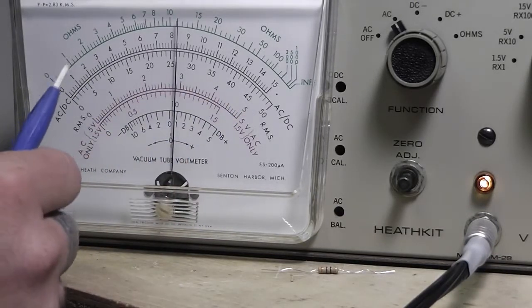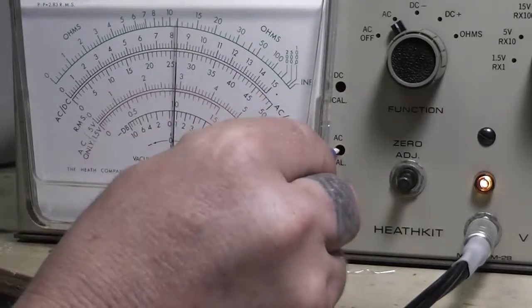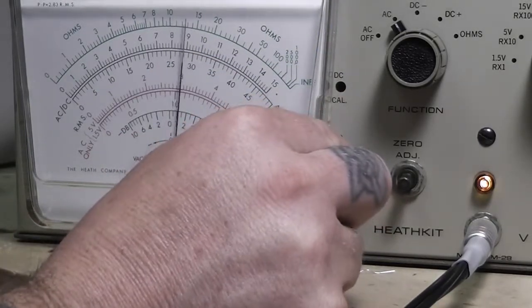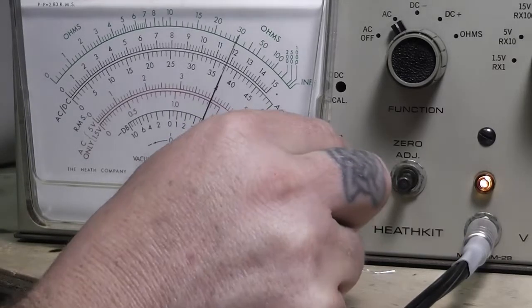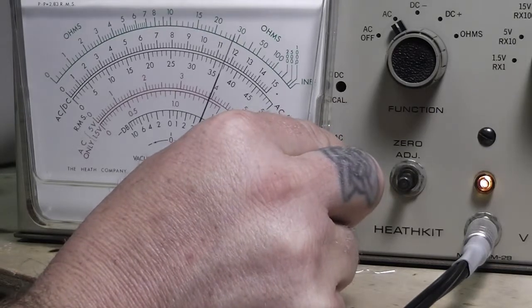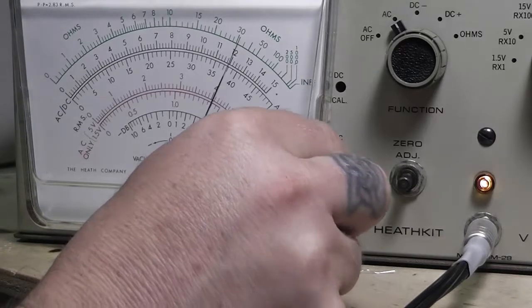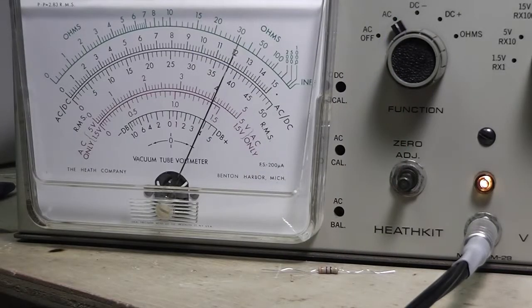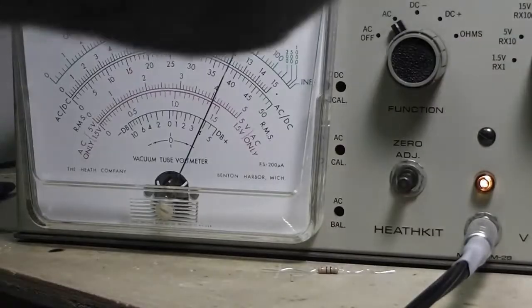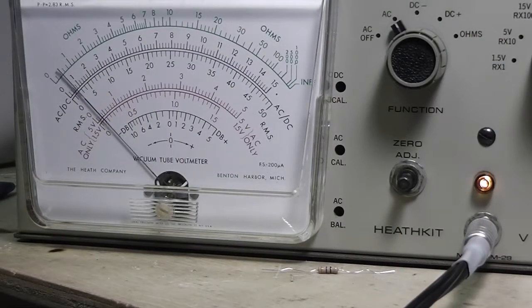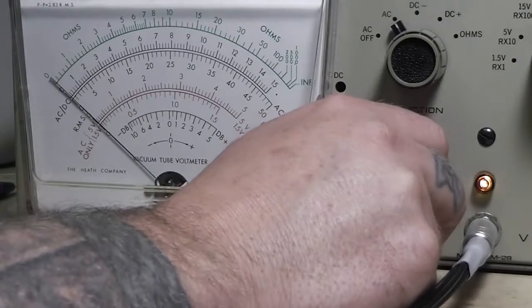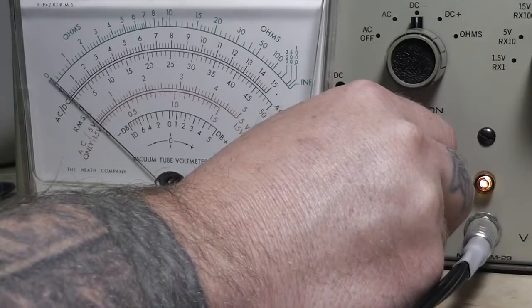Now we're at the 150 volt scale, so it's 10, 20, 30 up to 150. So set this AC calibration control until we read 120 volts, or wherever your line voltage is. And it's a little touchy as the other one. And there you go. Your AC side's set. Again, if you work with low voltage AC stuff, there's nothing wrong with taking it and putting it on your AC low voltage supply that goes up to 12 volts or whatever, 10 volts, bringing this down here and adjusting that to get it to read exactly right. Okay, and then put that back there.